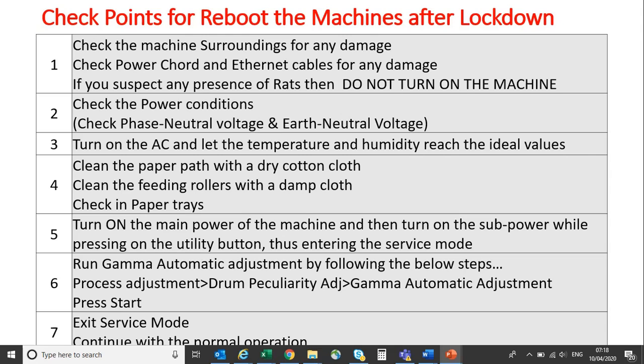Once you enter the premises after lockdown is over, check the machine surroundings for any damage to the power cord or Ethernet cable, or any presence of rats near the machine. If you find any presence of rats inside the machine, please don't switch it on. Please call an engineer to check the machine thoroughly.